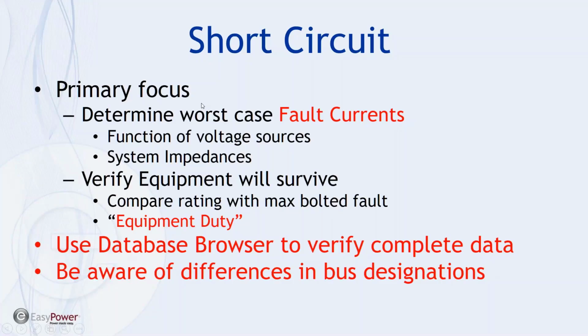Okay, so the point that I want to make is that the primary focus of a short circuit analysis, or short circuit study, is to determine the worst case fault currents and then verify the equipment will survive in that case. Well, that requires comparing the rating that the manufacturer has presented on its data sheet with the current that we're predicting in the worst case three-phase bolted fault. And as a result, if we haven't included that rating and we haven't made the connection between our components and the device library, we're missing a big part of the function of short circuit. And my point is this: the tool will do the heavy lifting here. We just need to be sure that we have the data loaded into the model. Okay, I'll quit beating on that one.